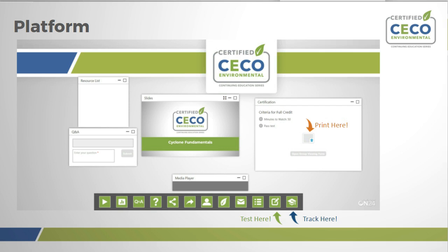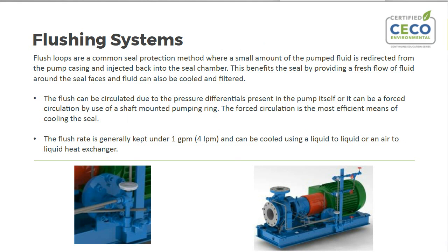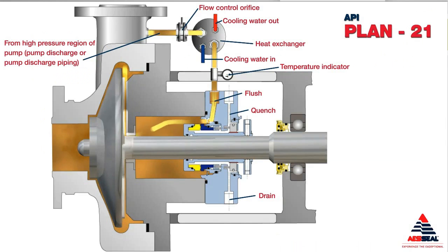So, going back to the flush systems, the next slide shows that Plan 21 in action. You can see that it's coming off of the discharge, going through the heat exchanger, and then down into the seal chamber. At the heat exchanger, the flush is cooled, and it is injected back into the seal chamber, keeping that seal much cooler than the actual pumpage itself.